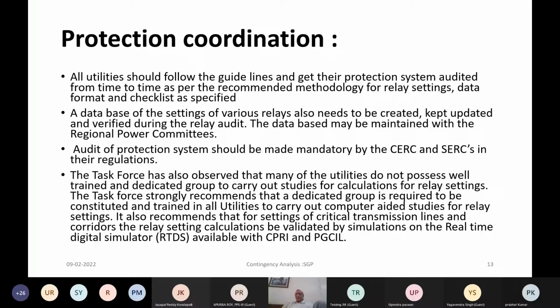For different contingencies, if there are any setting changes which are necessary for coordination of control actions with respect to the protection schemes, this becomes important, so that there is no undesirable protection operation. And we'll discuss more in detail in the afternoon session. What are the protections which are susceptible for undesirable operation during system disturbances?